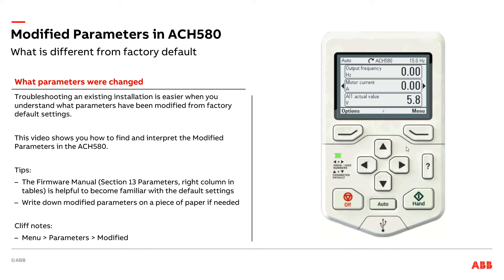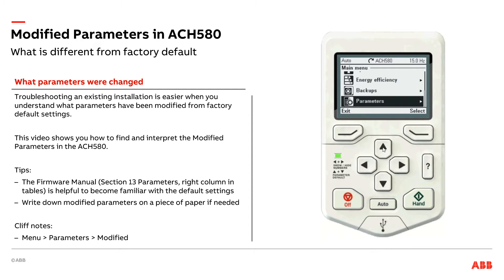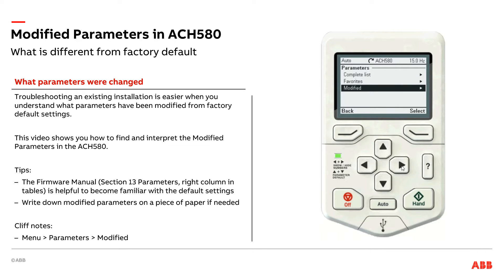I'm going to come up here to menu. I can either scroll down, but there's a shortcut trick where if I hit the up button, it'll take me straight to parameters. Or I could have scrolled down to parameters, hit the right arrow, and I've got my complete list of parameters. If I had created a favorite list or my modified list of parameters, I'll come down to modified, hit the right arrow, or I could hit select. And right now I have details on everything in this drive that has been changed from the factory default settings.